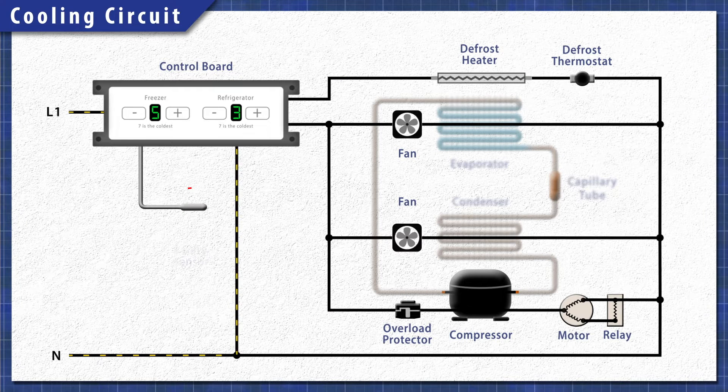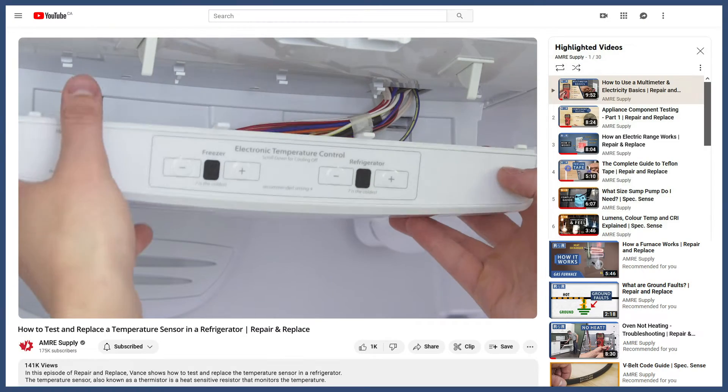Now if the sensor fails completely, then the compressor will not receive power and the refrigerator will not start. You can see how to troubleshoot this in the video linked below.